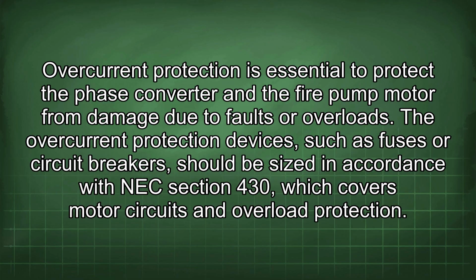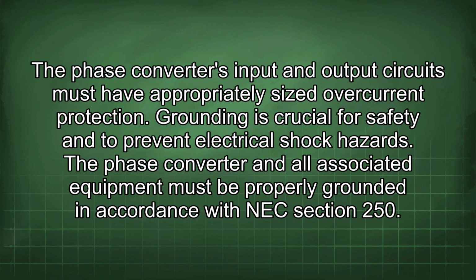Overcurrent protection is essential to protect the phase converter and the fire pump motor from damage due to faults or overloads. The overcurrent protection devices, such as fuses or circuit breakers, should be sized in accordance with NEC Section 430, which covers motor circuits and overload protection. The phase converter's input and output circuits must have appropriately sized overcurrent protection.